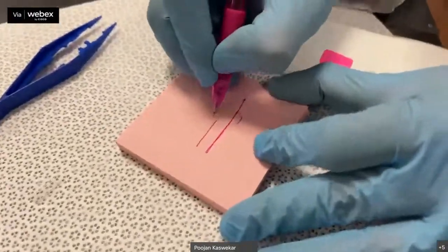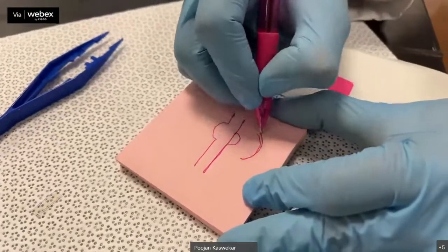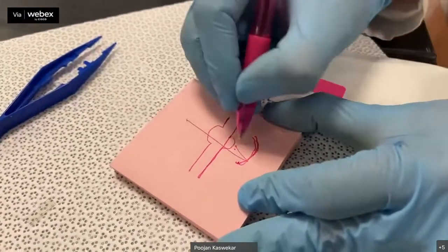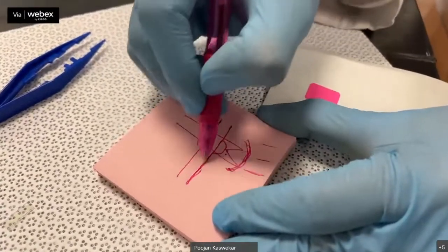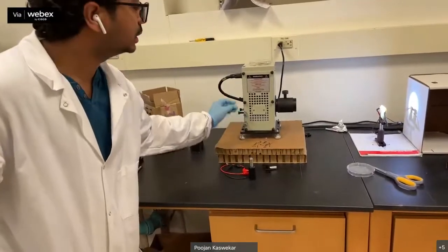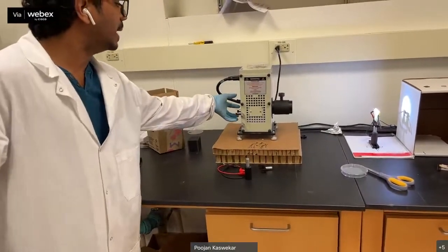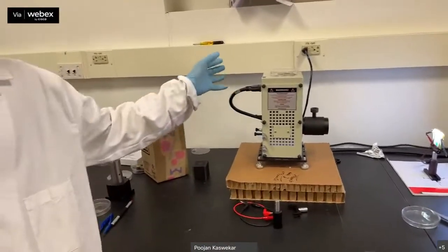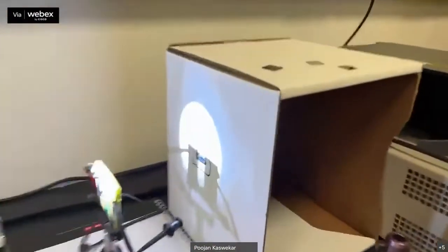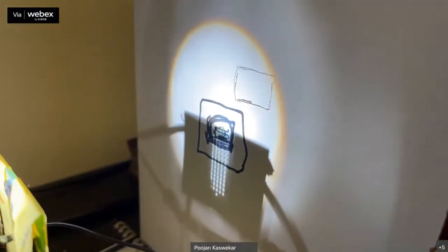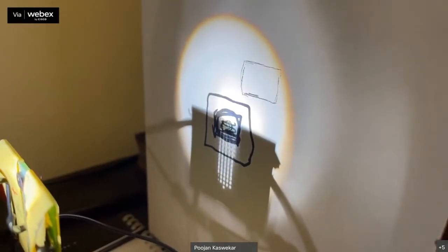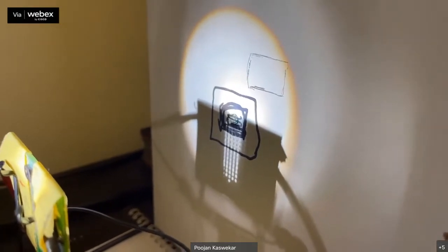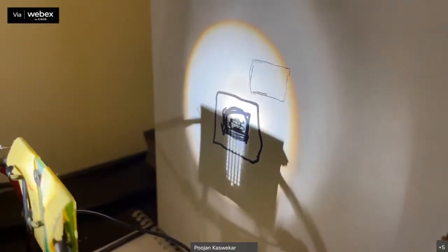This is the xenon arc lamp which is present there, and there is a rear reflector in the back of that one. It will reflect the light to the outer wall. So we can adjust the rear reflector using the back knobs, and we can adjust the height of this xenon arc lamp using the side horizontal and vertical positions. With the horizontal and vertical positions, you are adjusting the xenon arc lamp itself, and with the rear adjustment, you are adjusting the reflector. When I am adjusting the horizontal position, it will move my illumination left and right. I don't know if you guys can see that, and this will adjust the illumination in the vertical position.